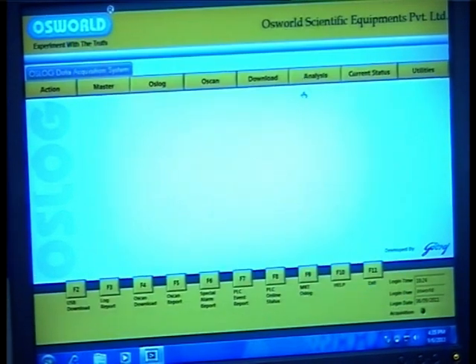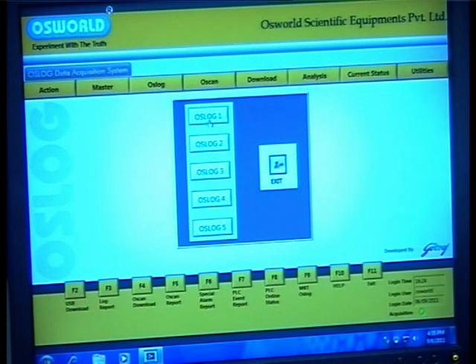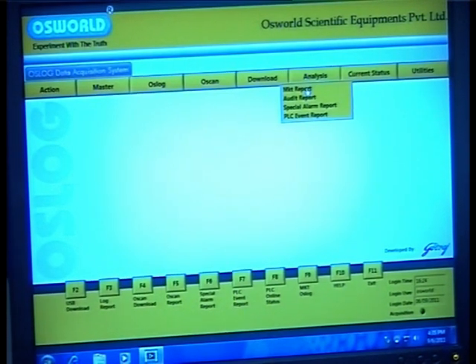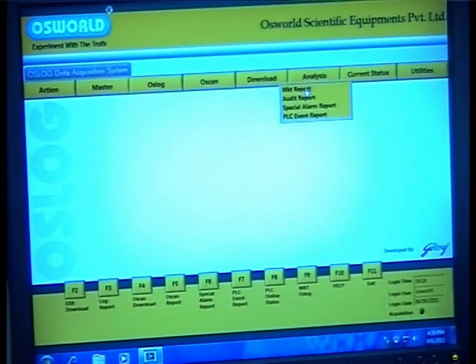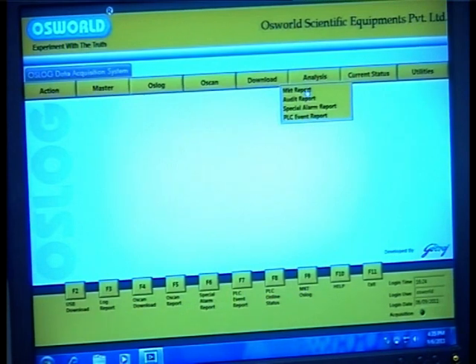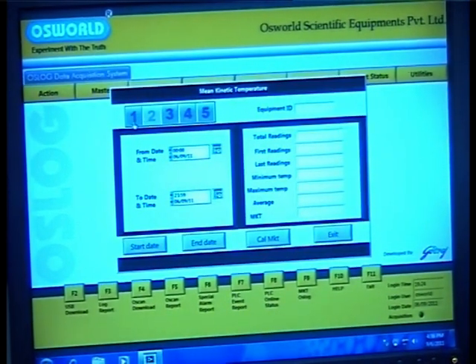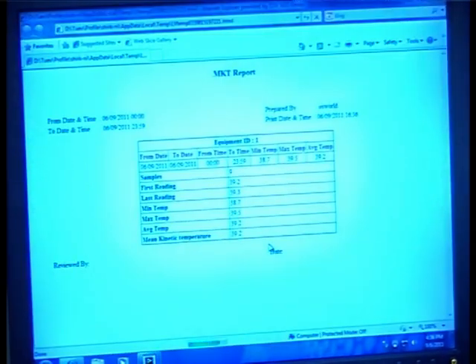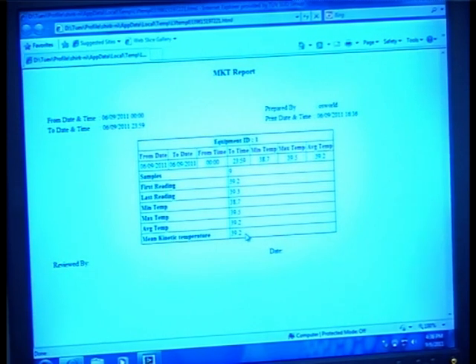Moving on to MKT reports and audits: I will now demonstrate how to generate two more important reports — the mean kinetic temperature (MKT) report and the audit trail report. The MKT gives a representation of the effects that temperature fluctuations can have on materials such as pharmaceuticals and food products. With the OSLOG software, the MKT can be calculated for any number of dates. To generate the MKT report, click on the analysis drop-down, select the MKT report tab, and select OSLOG 1. The mean kinetic temperature window opens up. Enter the time and date range and hit calculate MKT. A report is generated showing your first and last reading, minimum temperature, maximum temperature, average temperature, and finally your mean kinetic temperature.